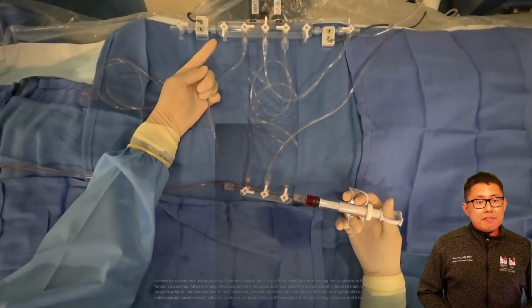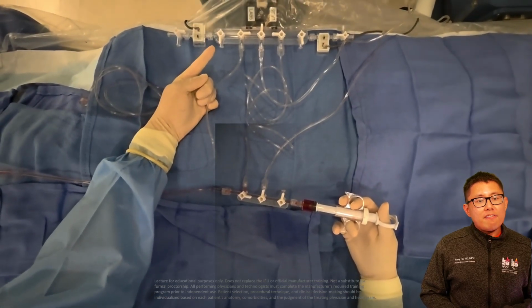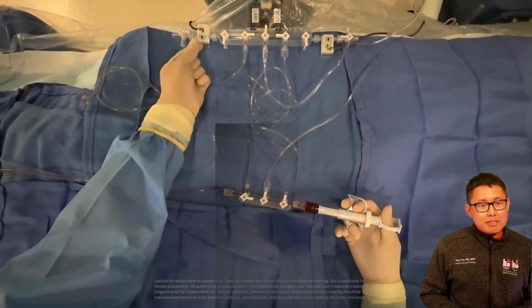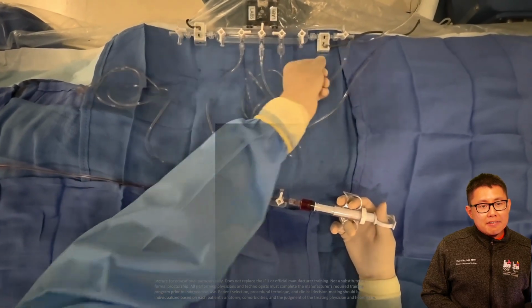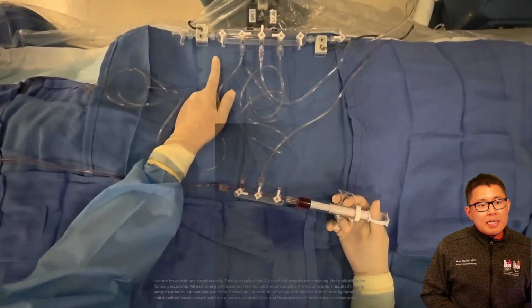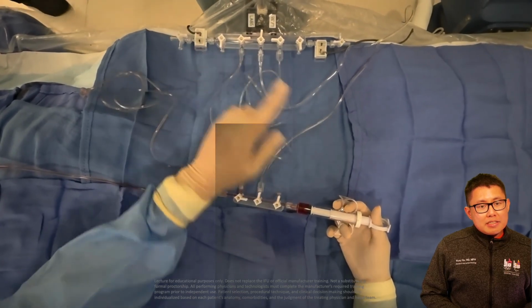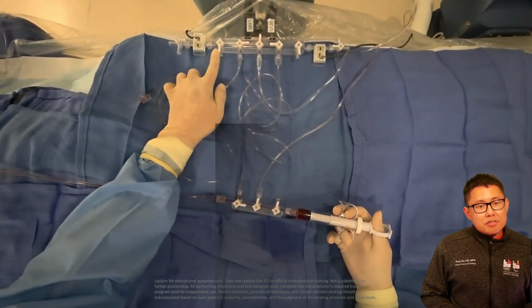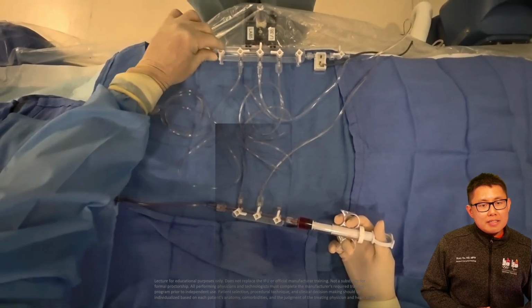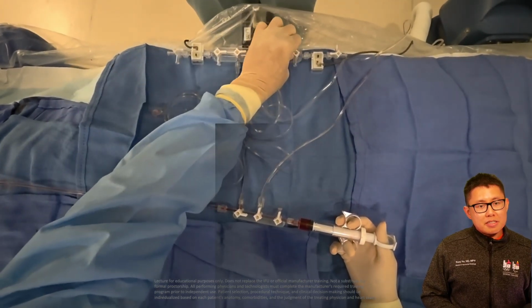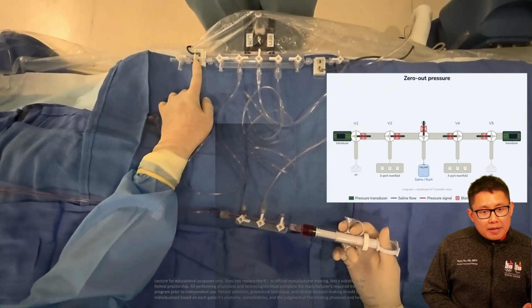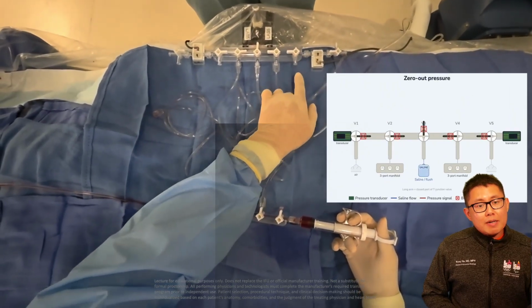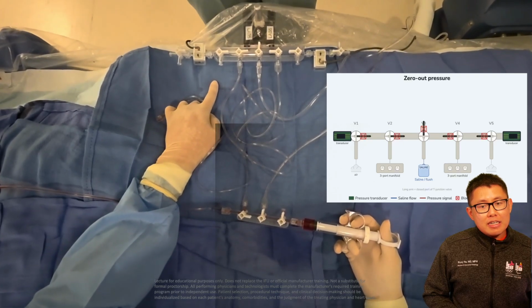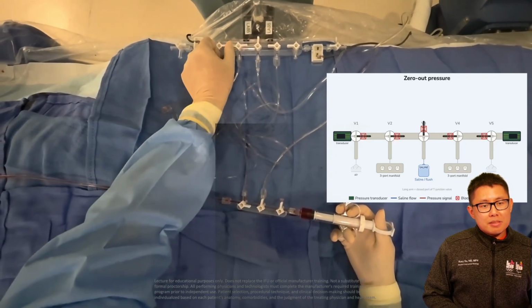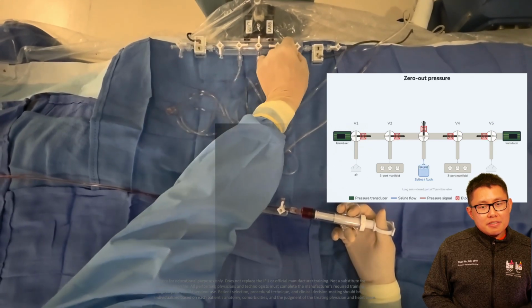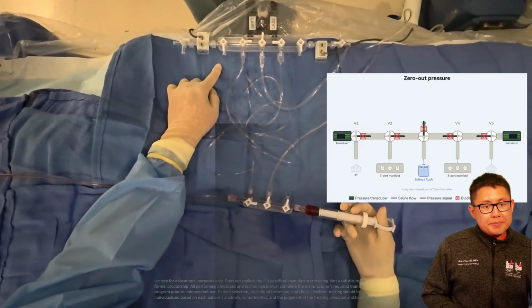In this 5-port manifold, you have V1 and V5, which are flanked by electronic chips, which are the pressure transducers you see over there that I'm holding with my left hand on both sides. V1 and V5 are connected to air. The purpose is that it allows you to zero the left and right pressure sensors or transducers, which is what I'm doing here. If I put V1 pointing to the right and V5 pointing to the left, that allows a direct connection to air, and that allows you to zero the pressure transducer. So now let's turn it back off to air by having the long side pointing down.